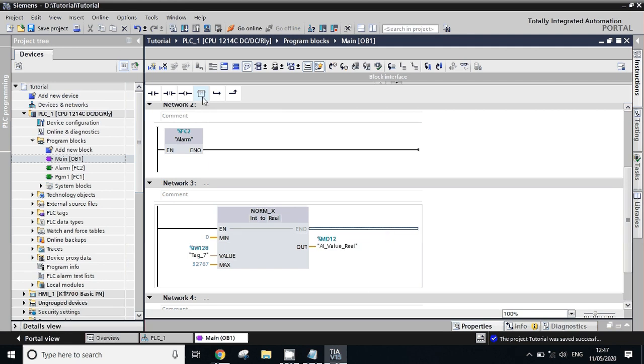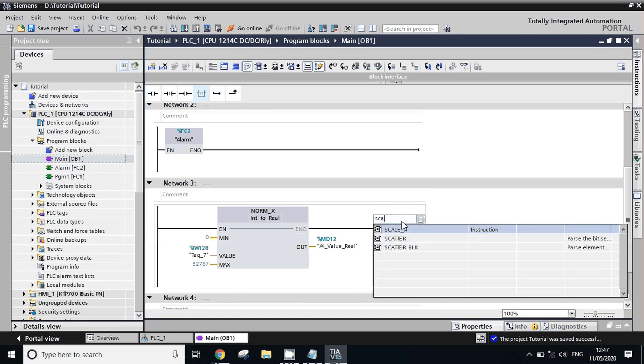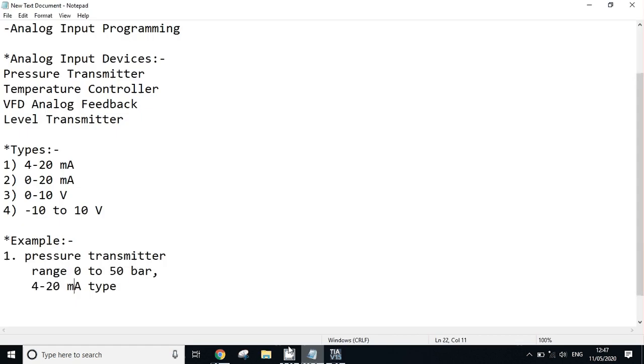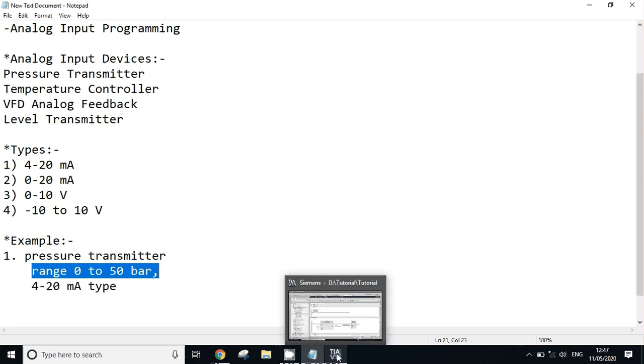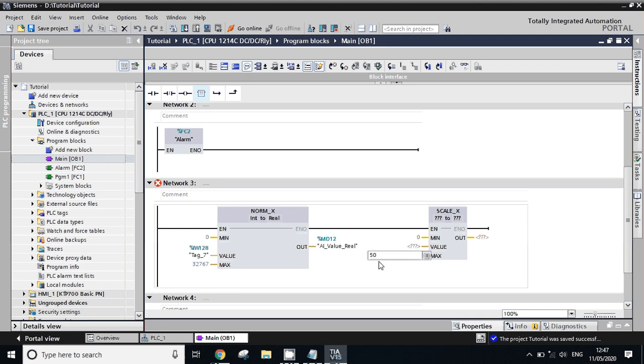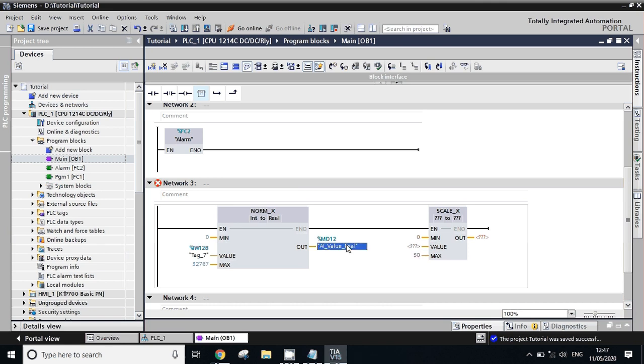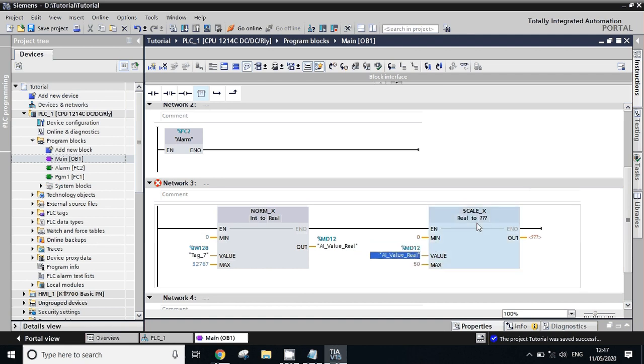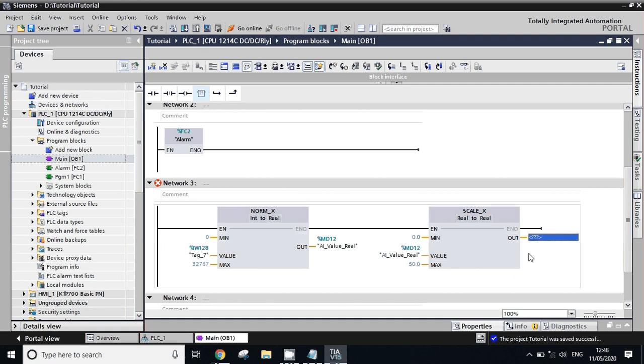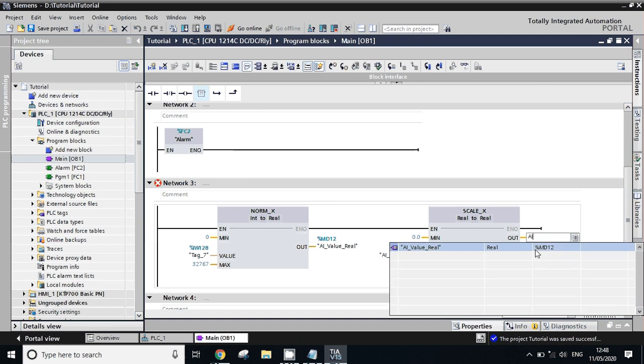Now we will take one more empty box for scaling. Take SCALE_X. What is the range of our transmitter? It's 0 to 50 bar, right? So minimum should be 0, maximum should be 50. And copy this address, just give it to here. Real. We can show in real also. Output: Analog input actual value.